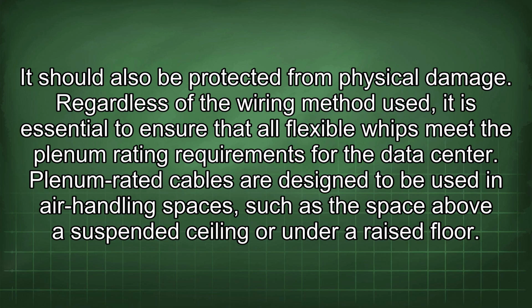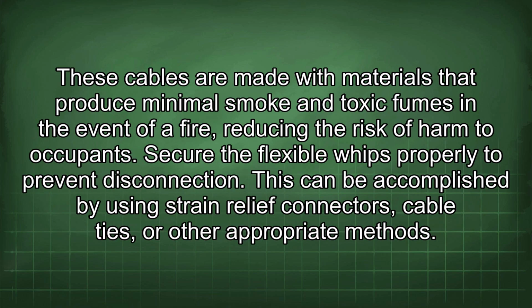Regardless of the wiring method used, it is essential to ensure that all flexible whips meet the plenum rating requirements for the data center. Plenum-rated cables are designed to be used in air handling spaces, such as the space above a suspended ceiling or under a raised floor. These cables are made with materials that produce minimal smoke and toxic fumes in the event of a fire, reducing the risk of harm to occupants.